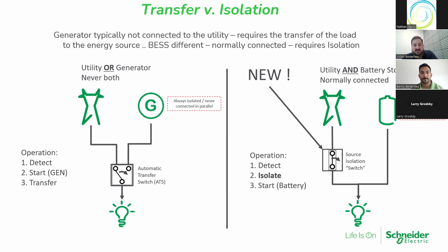And then you put it on the utility source itself. Well, that's just not providing you any isolation, because the moment you go to emergency, if there's another source to allow you to transfer that switch, you can't get power to those loads at that point because the inverter is tied in with the utility. So an ATS really doesn't fit the bill, and that'll be clear in an upcoming one line. Meanwhile, to Benny's point on the isolation side, with an isolation switch, you can run parallel with both of them until you have an issue with your main power source, and then it isolates, and you've still got your inverter connected to your loads. So I just wanted to clarify that point so that you can follow the one line.